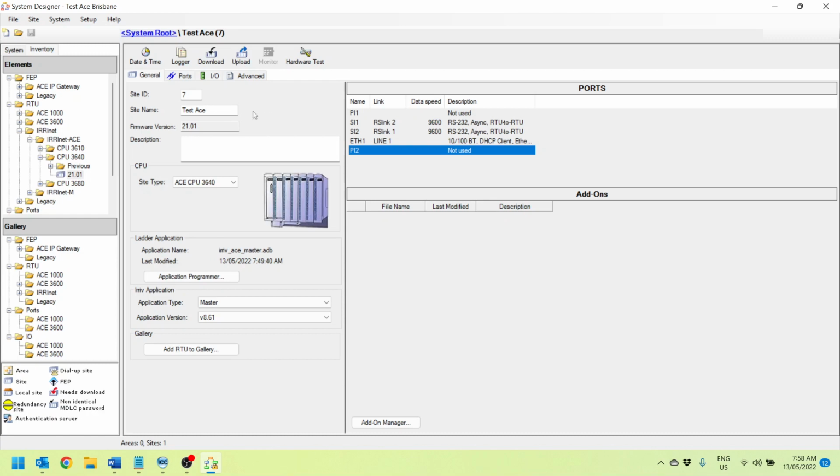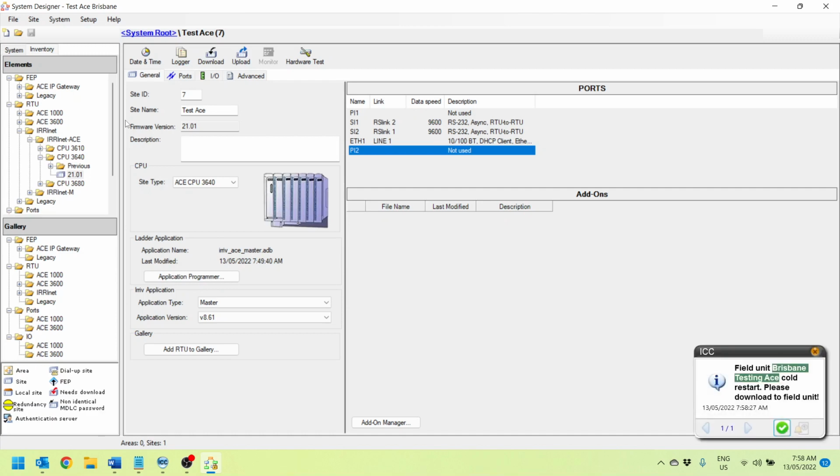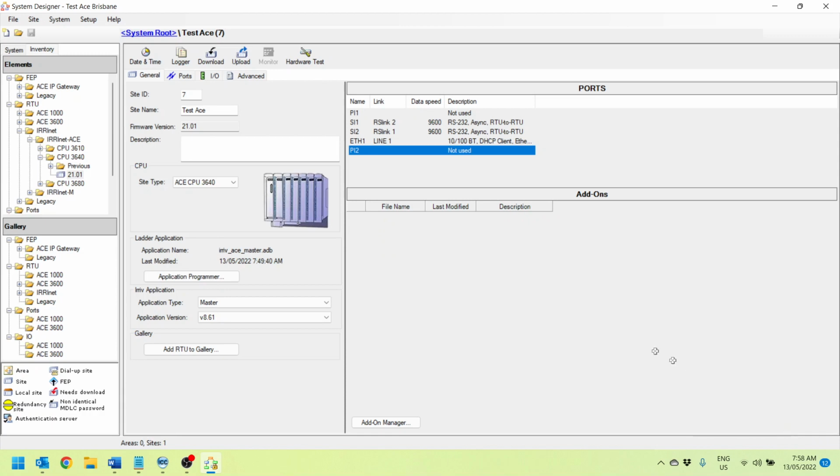And if this is on a server with controllers that have multiple network paths, we will need to download the network file. But if the controller talks back to the server directly and all the other controllers talk directly, then the network file actually isn't required. In this case, we've got the cold restart already without a network file, so we won't worry about it.